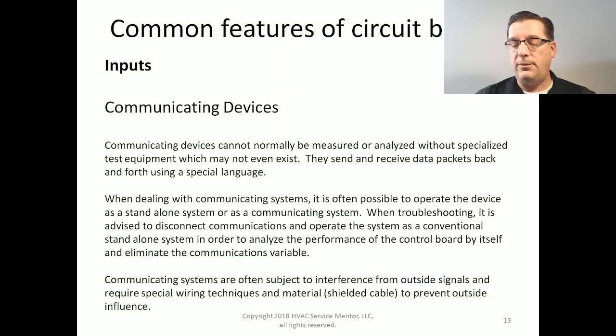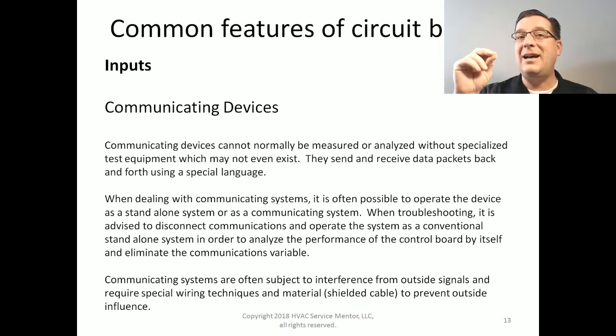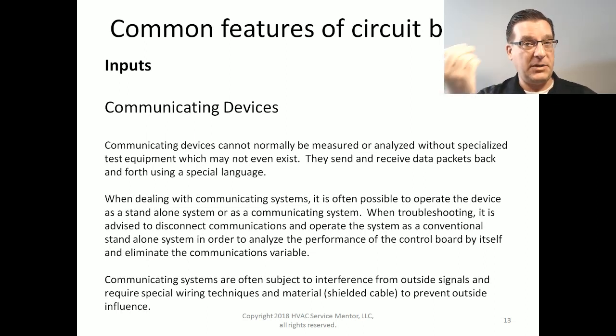Now, when it comes to communication, it's a little different, right? The USB cable or the Ethernet cable that plugs into your computer that sends data back and forth, that's communication. When I have something that is just a switch opening and closing, that's not communication. When I have an analog sensor, that's not communication. Communication is a send and return. It's literally talking back and forth between two control boards in a specific control language. Communicating devices cannot normally be measured or analyzed without specialized test equipment. And on the residential side, that specialized test equipment probably doesn't even exist. We're getting there, but we're not there yet.